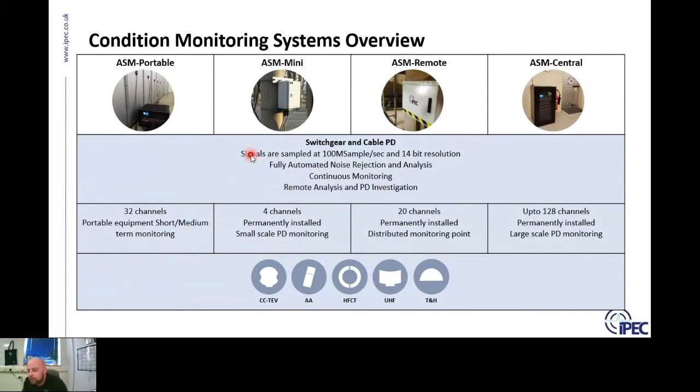So we do that in two phases. Phase one is that acquisition - 100 mega samples per second, 14-bit resolution. So that digital data, we've got a lot of data for every individual channel detected by the HFCT sensor.